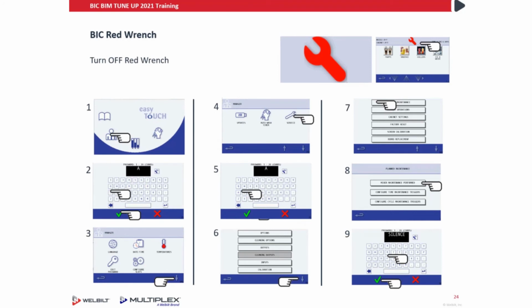To turn off the red wrench on the BIC, you will go first to the manager's menu, enter A as your password, then arrow down twice to see the service wrench. Once in the service wrench, you'll enter A as your password again, arrow down once, then you'll go to planned maintenance.